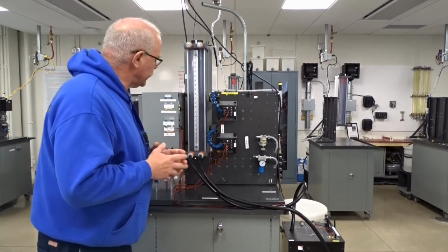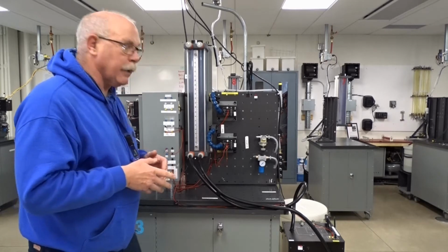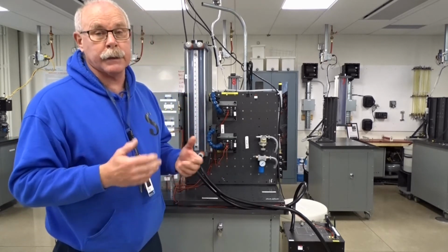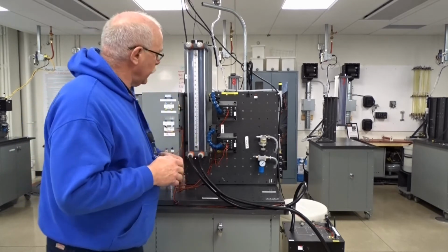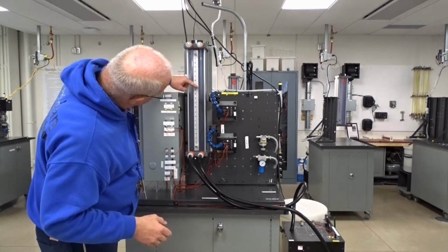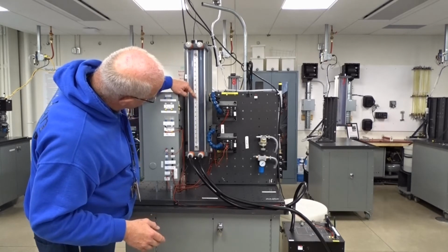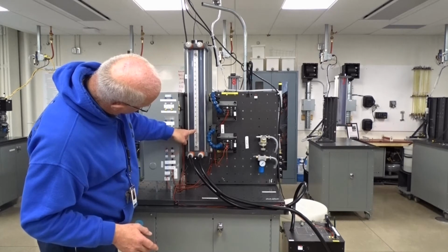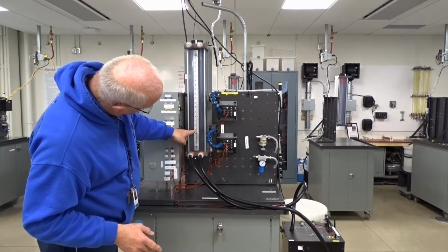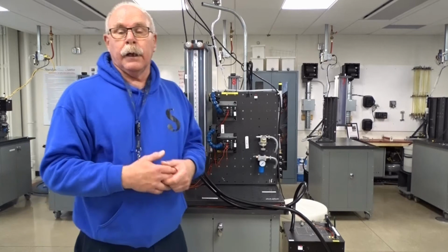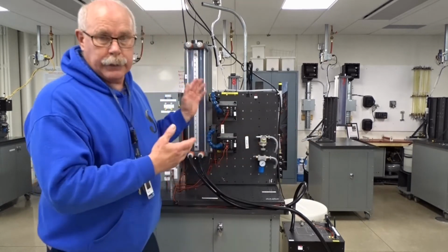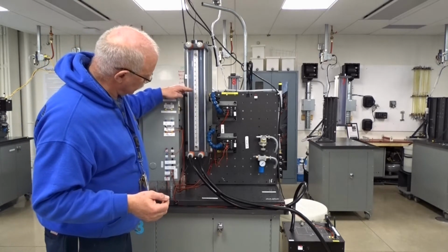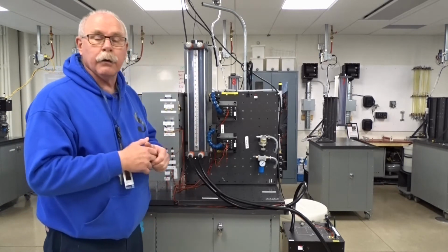Okay, so what we see here is we actually have a deadband to this process. Deadband in this case is necessary. Now, if you notice, it comes up to about 12 inches and it shuts off, and then it drains out down to about 5 inches. And what we have is a deadband between those 2 numbers. Our upper range value is 12, our lower range value is 5.